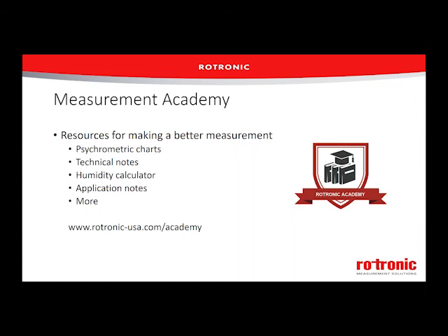Uncertainty and guard banding and the issues that are coming out of the new ISO 17025 standards are going to make the issue of pass-fail, the issue of out of tolerance, become more and more complicated. And I just wanted to put out to everybody on this webinar that we are somewhat on the leading edge, right, Michael, in terms of guard banding and dealing with the new ISO standards. We had to deal with this last winter.